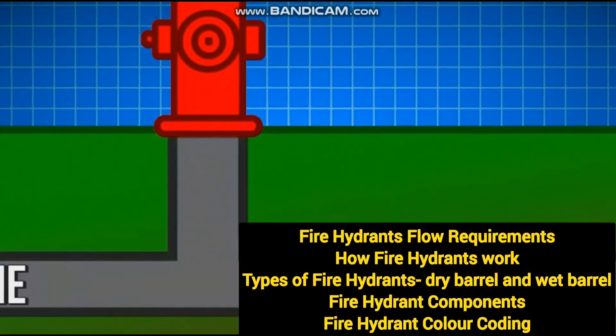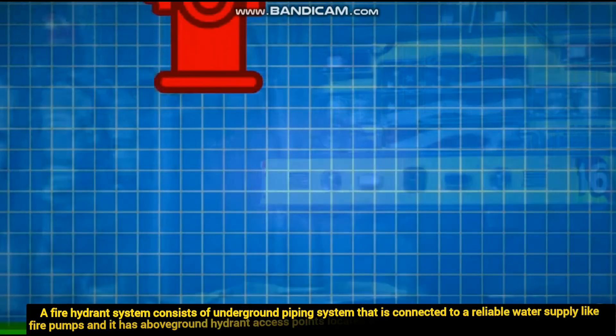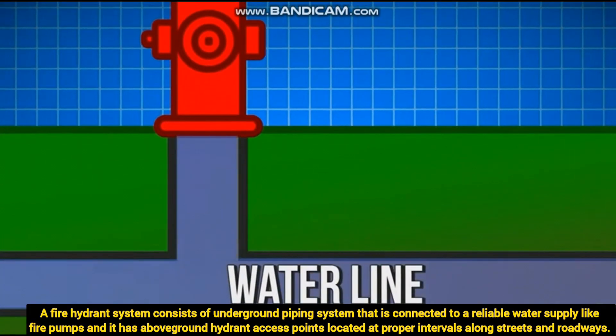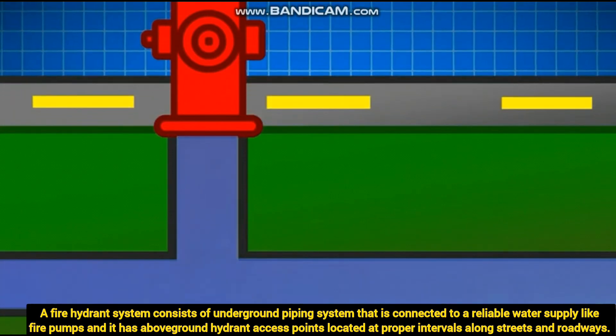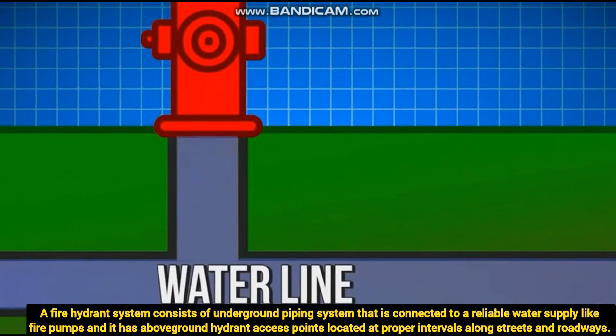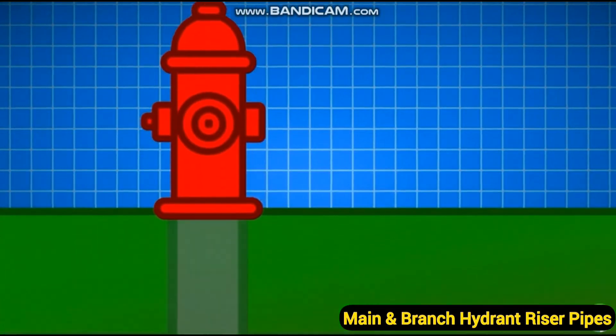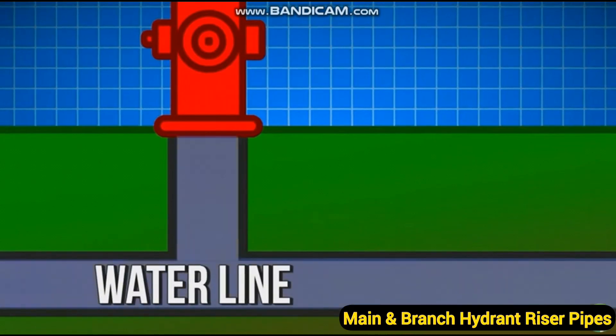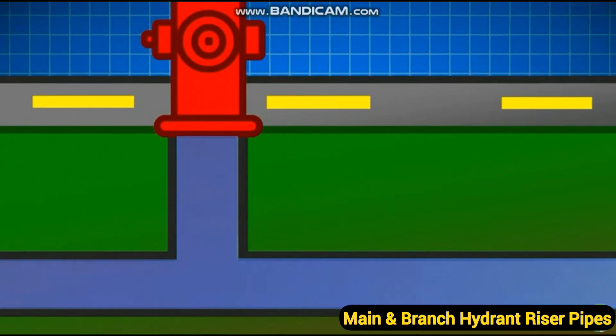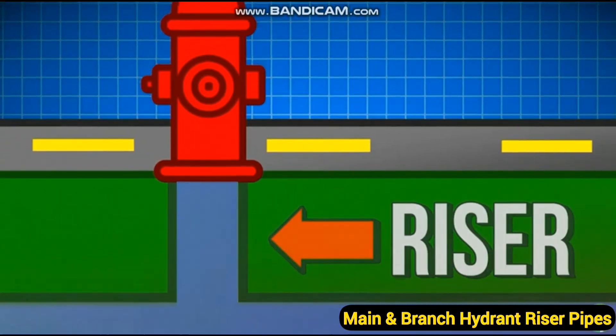Hello friends, welcome back. In this video we are going to see lots of important information related to fire hydrant systems. A fire hydrant system normally consists of an underground piping system which is connected to a permanent water supply like fire pumps, and it has above-ground hydrant access points located at proper intervals along the streets and roadways. Usually from the main line we take a branch line for the hydrant installation with a 6-inch pipe size to limit the pressure drop and also for higher flow capacity.